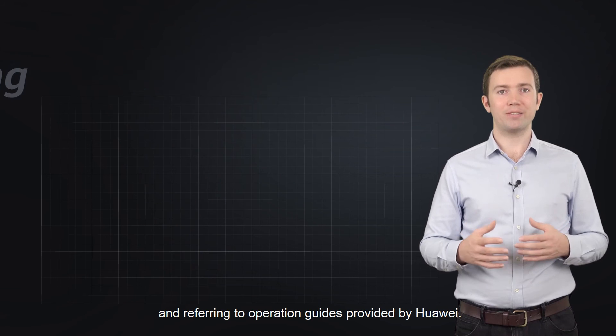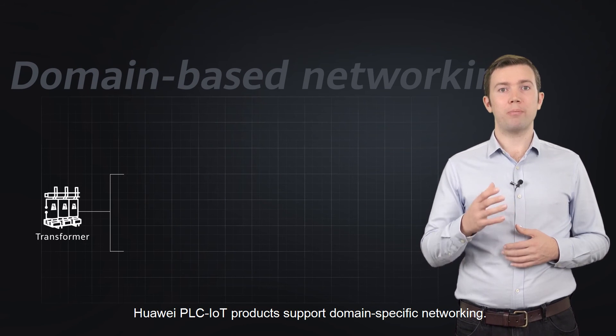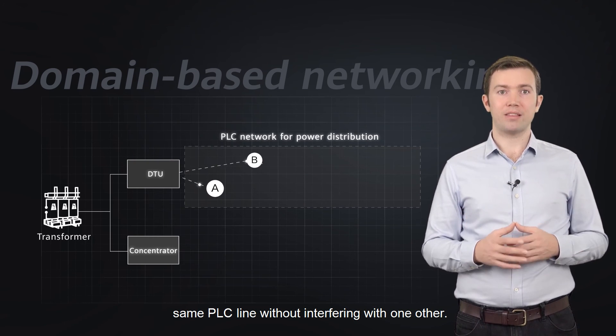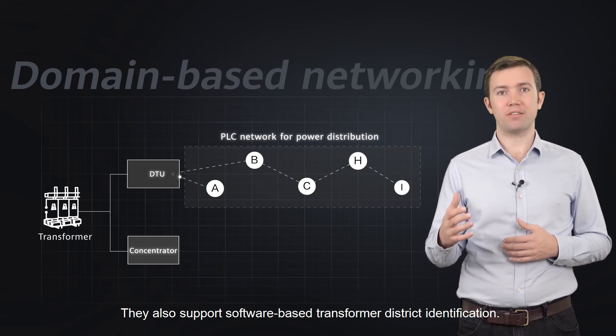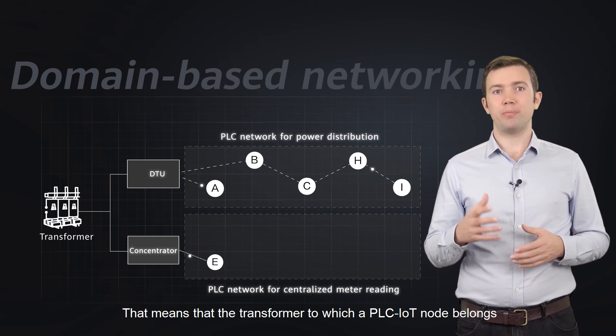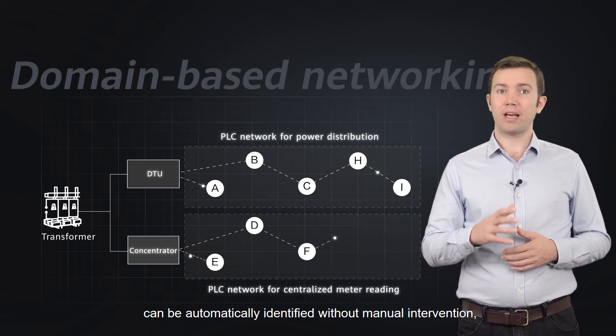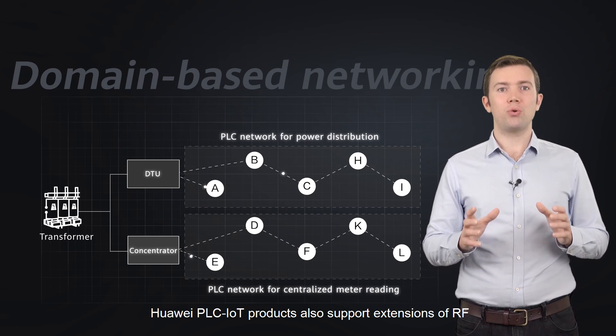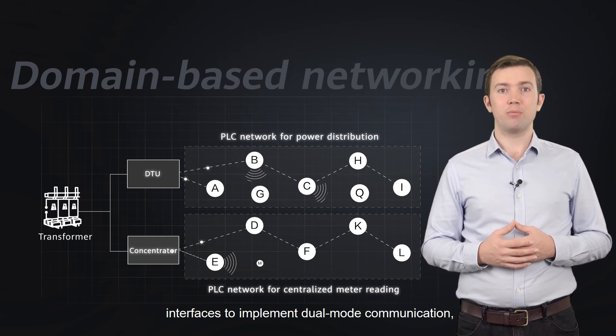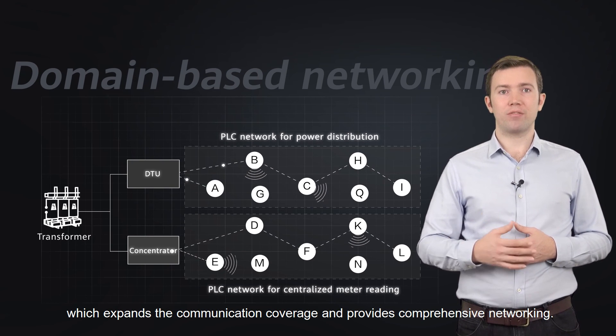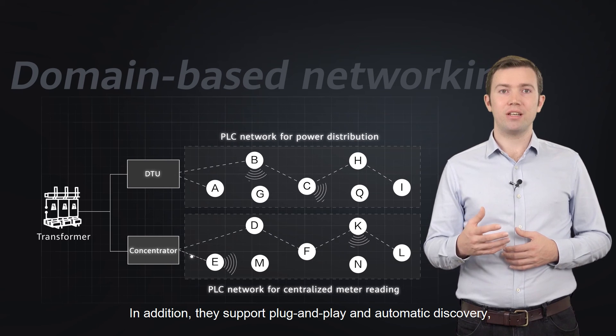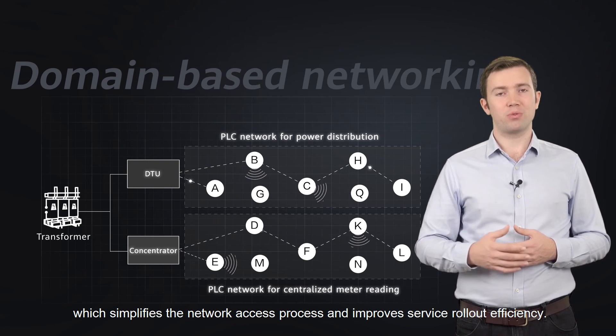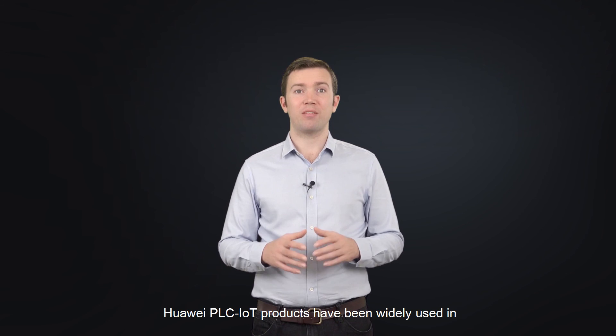Huawei PLC IoT products support domain-based networking. Multiple PLC networks can be built on the same PLC line without interfering with one another. They also support software-based transformer district identification, meaning the transformer to which a PLC IoT node belongs can be automatically identified without manual intervention, simplifying installation and deployment. Huawei PLC IoT products also support extensions of RF interfaces to implement dual-mode communication, expanding coverage and providing comprehensive networking. In addition, they support plug-and-play and automatic discovery, which simplifies the network access process and improves service rollout efficiency.